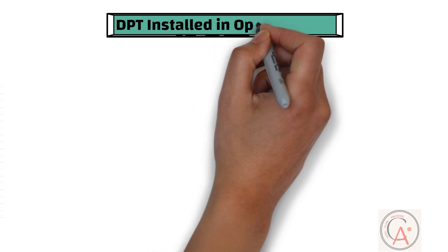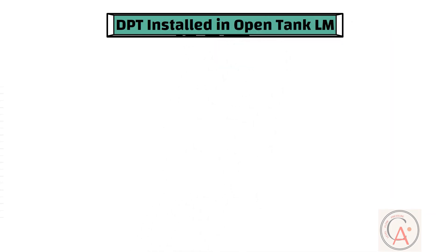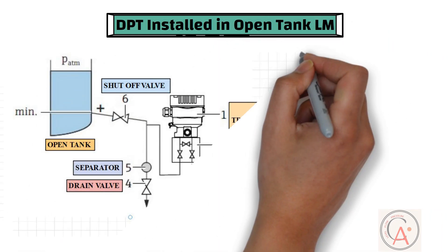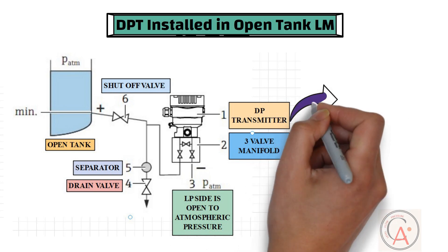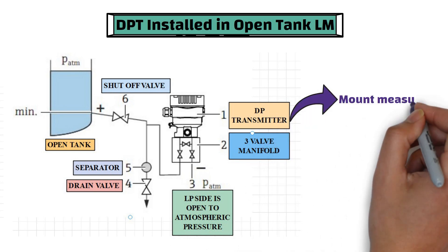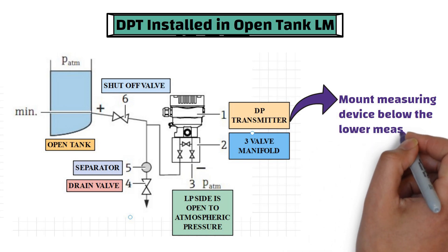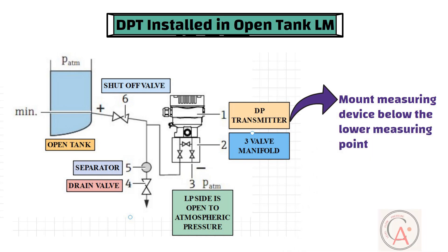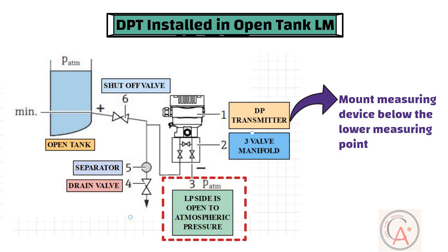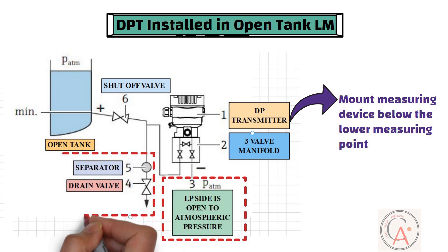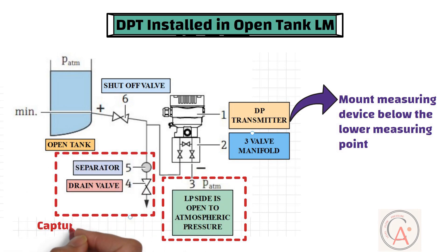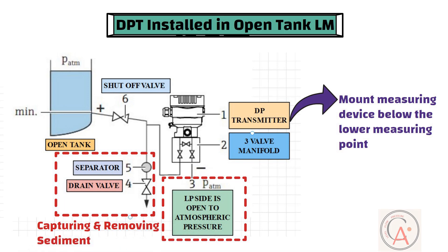First of all, let's start with the condition when a DP transmitter is installed for level measurement in an open tank. As you can see from the diagram, when liquid level measurement is done in an open tank, it is advisable to mount the measuring device below the lower measuring point so that the impulse lines are always filled with liquid. The low pressure side should be open to atmospheric pressure. Additionally, a separator and drain valve is useful for capturing and removing sediment when measuring media with solid parts such as dirty liquids.